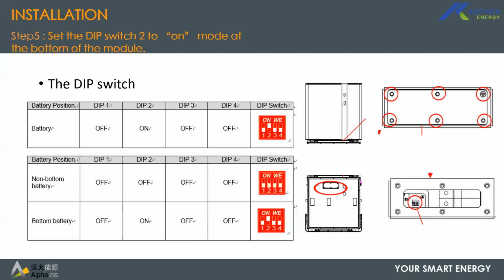So your bottom battery, or the last battery on your chain, if you have more than 2 batteries, you would need to set the DIP switch number 2 to on on the bottom battery. All other batteries, that is all the top batteries, their DIP switches have to be off, so you don't need to set anything. And on the last battery of the chain, or the bottom battery if you have 2 batteries, you need to set DIP switch number 2 on. If you have 1 battery, that's the bottom or the farthest battery, so you would need to set that battery's DIP switch number 2 to on.